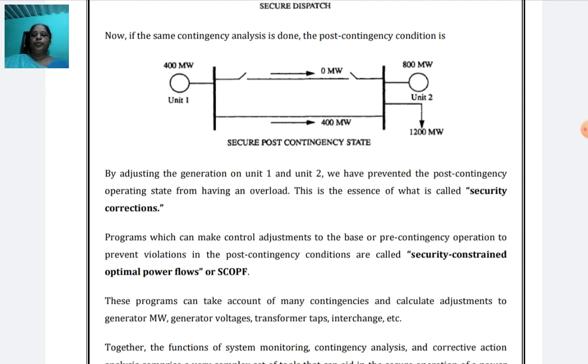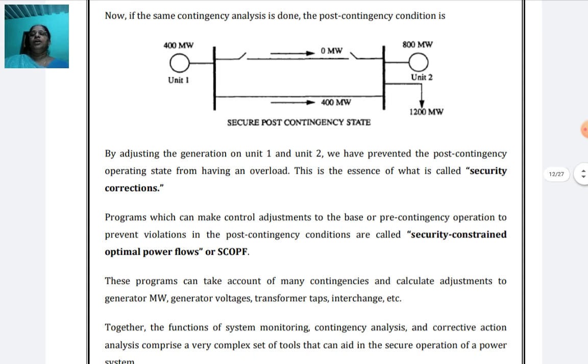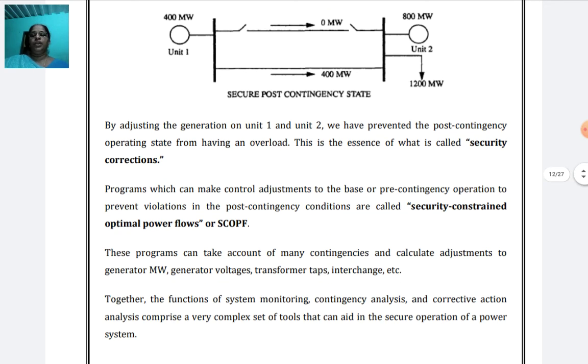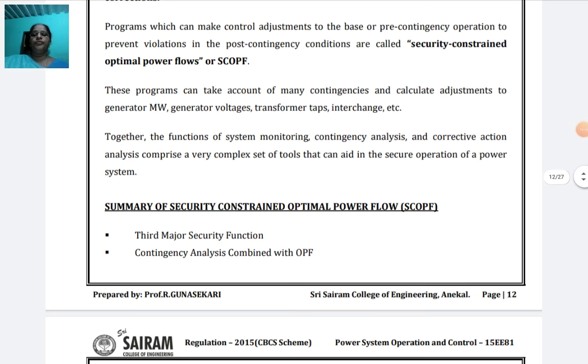So the program which can make control adjustments to the base or pre-contingency operation to prevent violations in the post contingencies is called the security constrained optimal power flow, that is SCOPF only. Now you see the summary of security constrained optimal power flow. Once we recall, there are three major security functions. First one is system monitoring, second one is contingency analysis, and the security constrained optimal power flow is the third major security function of power system security.